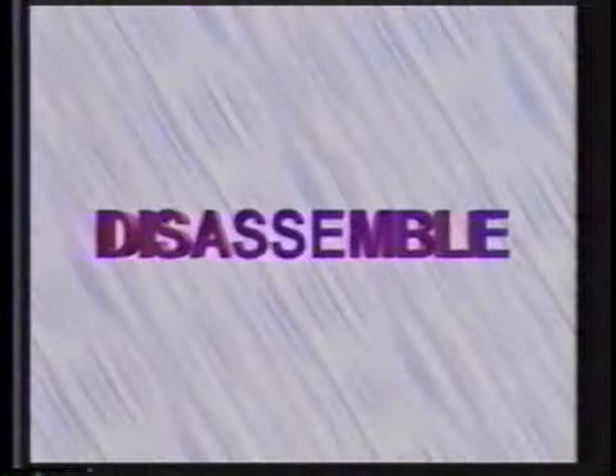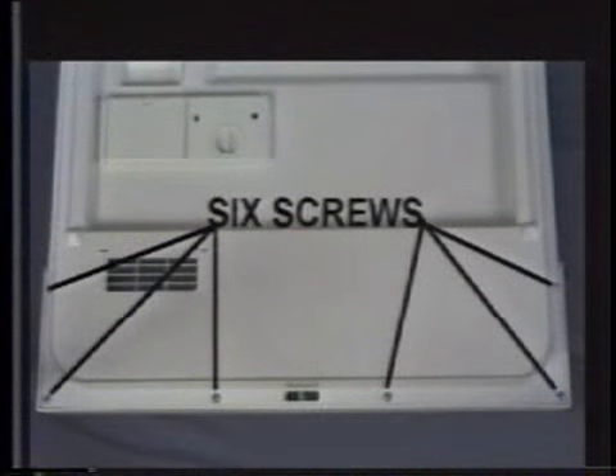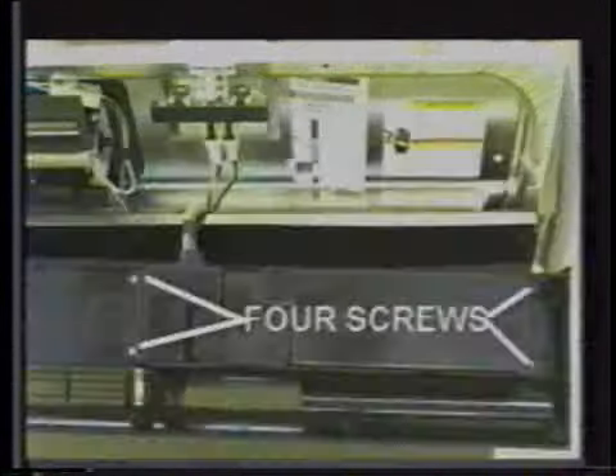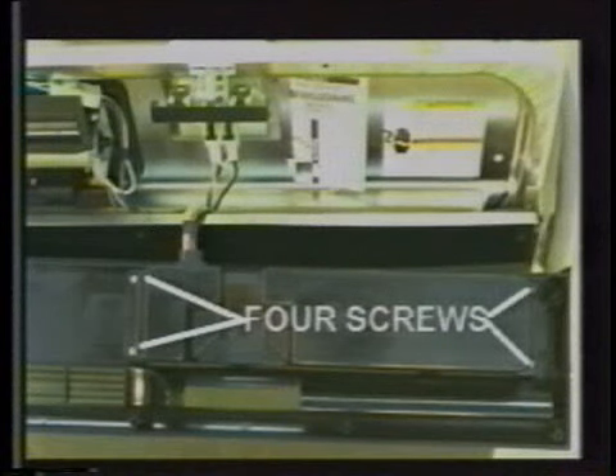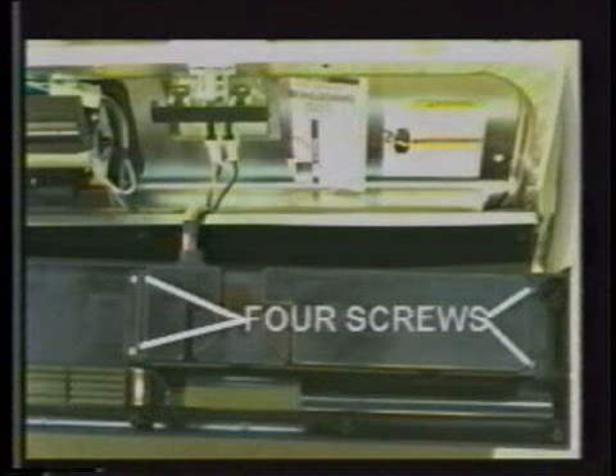All electronic components, except for the transformer and thermistor, are located in the control panel area. Therefore, to drop the control panel, we will need to remove the 6 screws as we did on the timer model. You should note that if you have a slimline model, you're going to have to remove the outer door panel first. Once the control panel is open, we then can get to the control board cover, and here this is held in place by 4 screws.